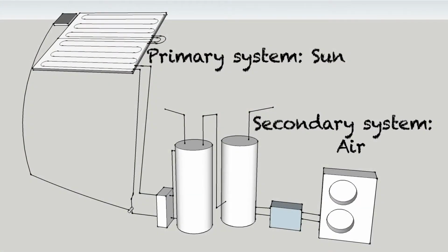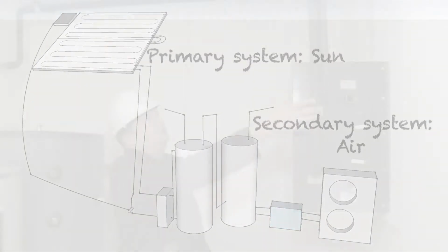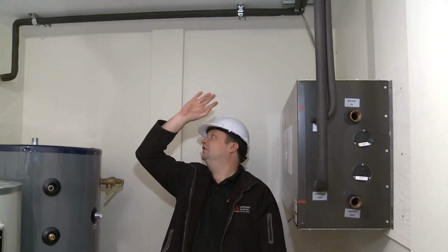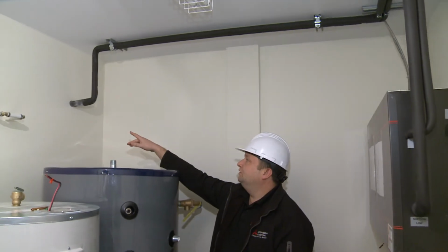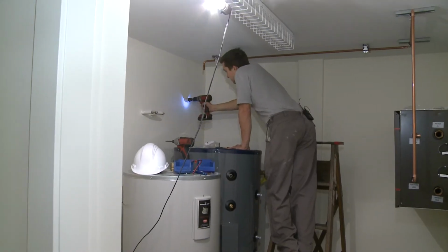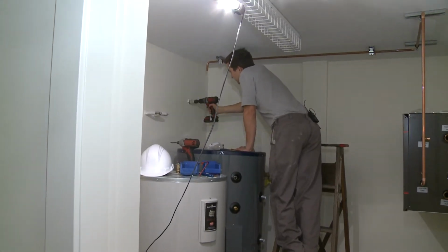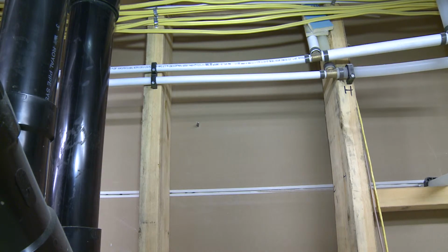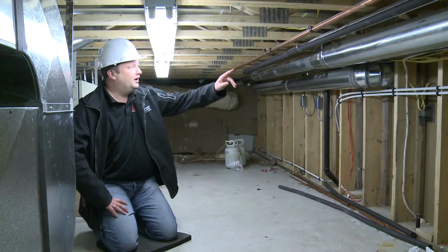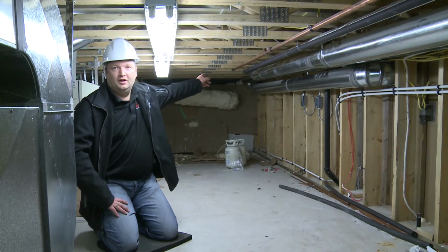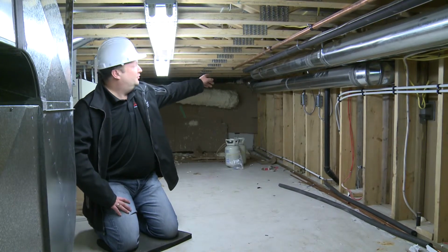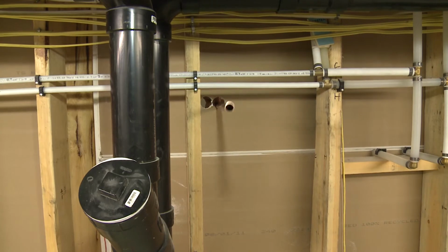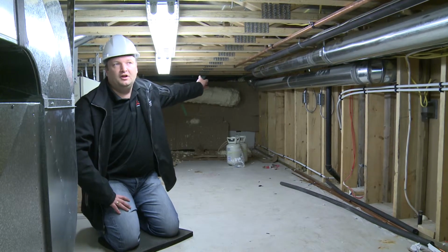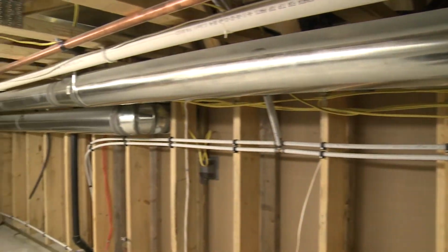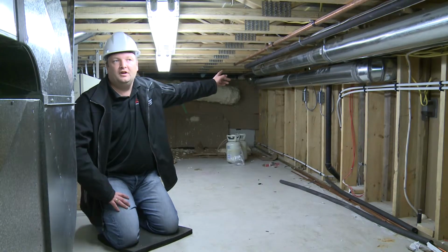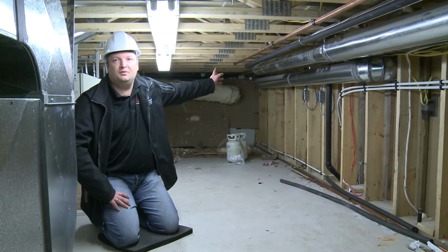This heat exchanger refrigerant pipework is installed along the ceiling and is then punched through the wall to go to the outside air source heat pump. I'll now take you back and show you where this pipework runs to. As you can see, the pipework runs down inside of the mechanical room to the end and is almost finished. We're just in the process of doing the final connections to the outdoor condenser unit. Once this is done, we can pressure test and commission the system and then start capturing the heat from outside to produce hot water.